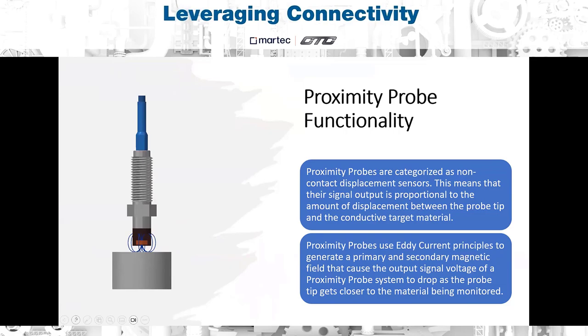Proximity probe systems use an electromagnetic field to generate something called eddy currents. They use a very sensitive impedance reading that they can linearize and transfer into an absolute measure of displacement from the probe tip to the material that it's monitoring, most commonly a shaft. Basically, as this target material gets closer to the probe tip or farther away, it very slightly affects the impedance in the circuit created by the proximity probe. And then the driver of the proximity probe, which we'll see in the next slide, can take that change in impedance and linearize it into an extremely accurate displacement measurement.